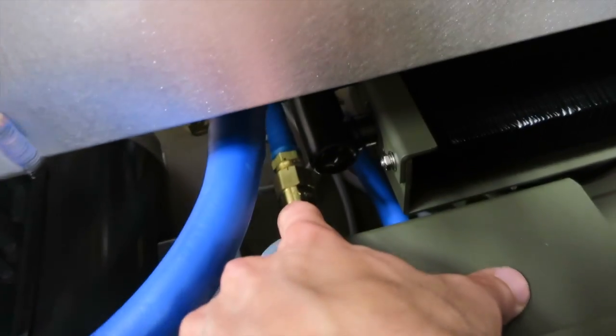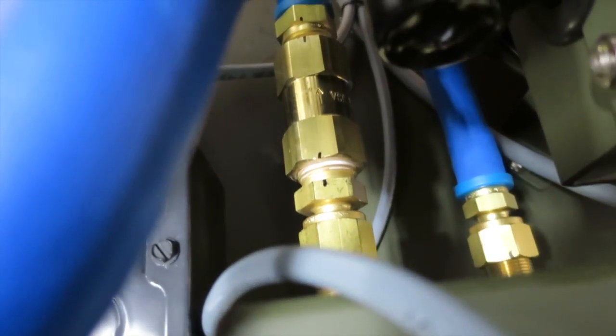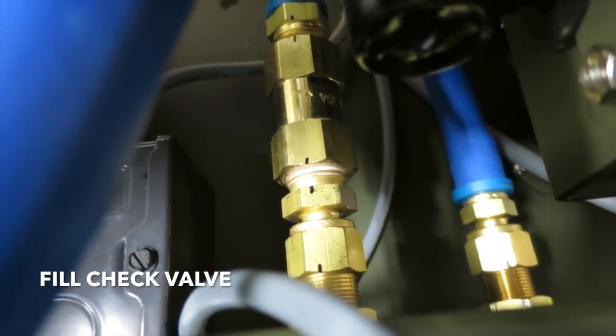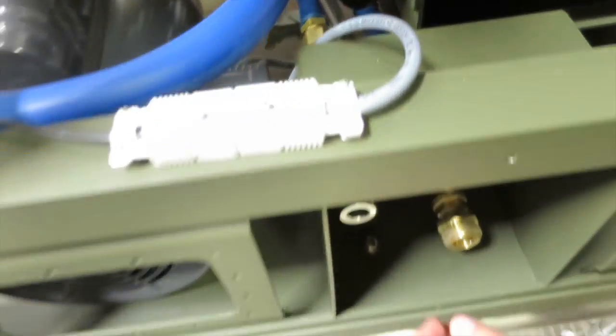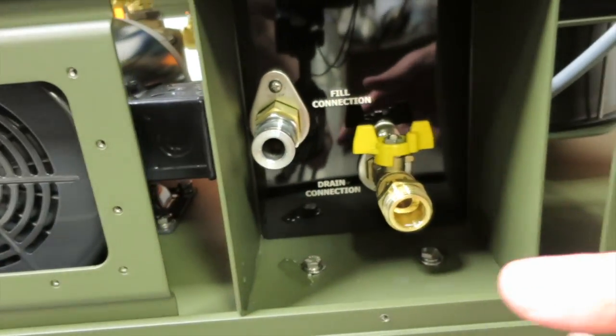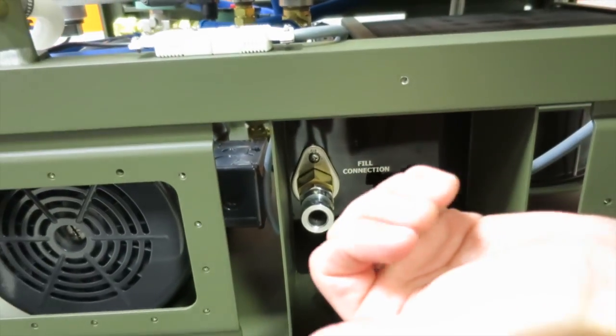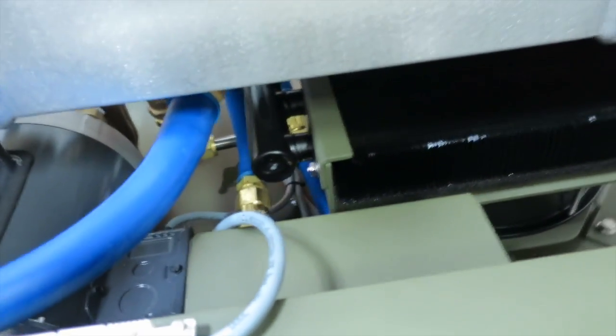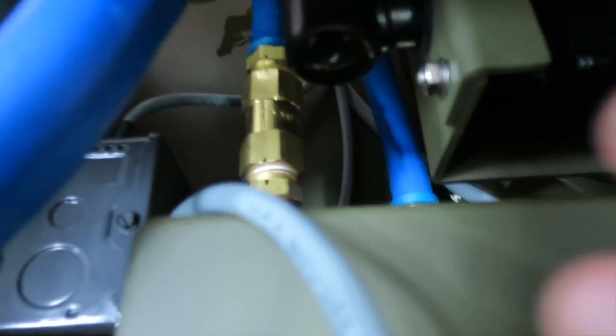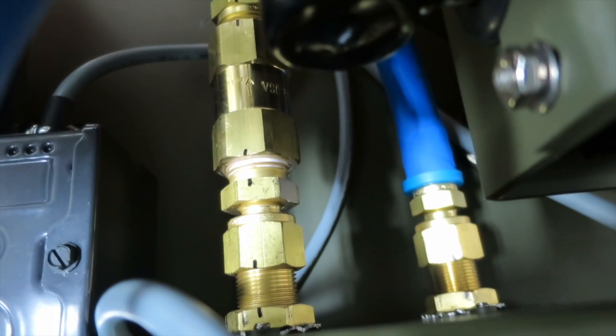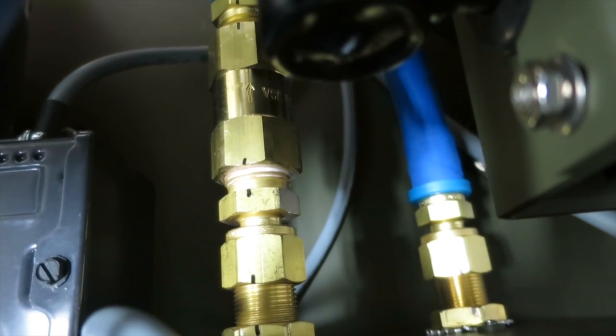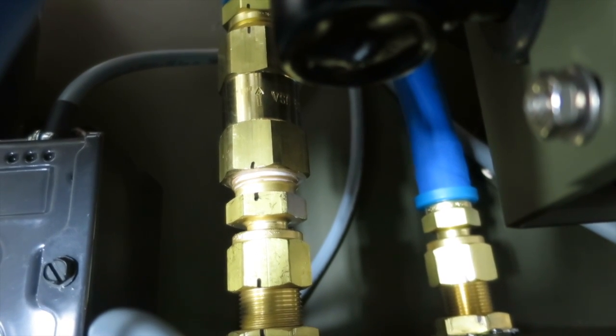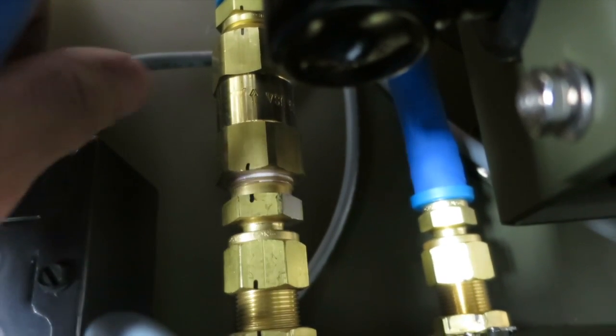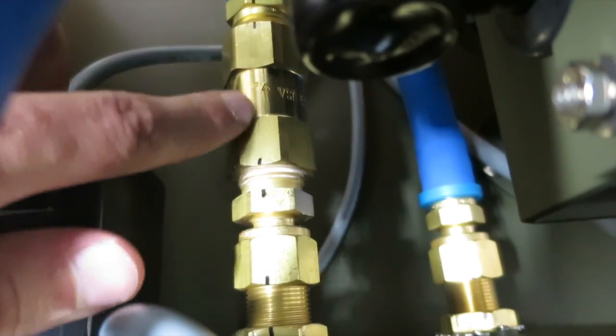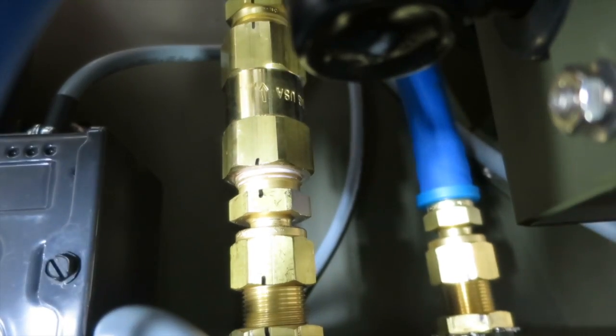Down there, the brass check valve, that is the fill check valve. That is connected to the cam and groove fitting on the front right here. Whenever you're filling this up, that allows us to not have water flowing back out when you remove the cam and groove fitting. So that's the fill check valve. Always, when you're replacing it, there's a small arrow, and the direction of the arrow is in towards the water recovery system. So you'll notice it's facing from there to there. It's kind of hard to see.